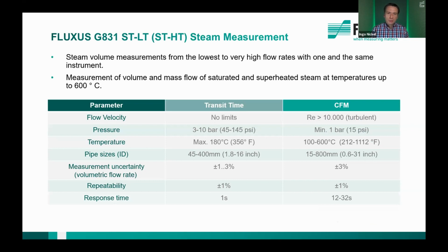We have solutions for low temperature and high temperature steam. There we have different measuring principles to cover the low temperature steam area, but also the high temperature, superheated steam area. Here you can see the overview, and you see the difference in transit time in the CFM. CFM is the mode for the high temperature steam. With the CFM mode, we can reach applications for superheated steam up to 600°C.